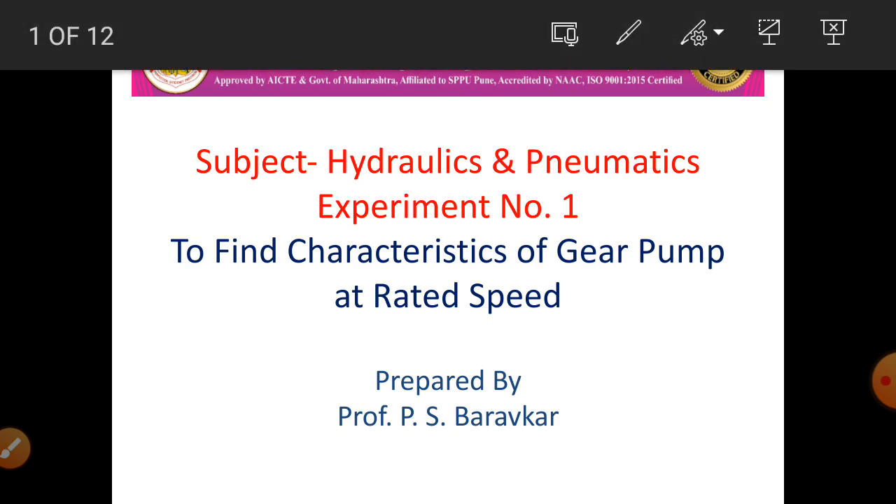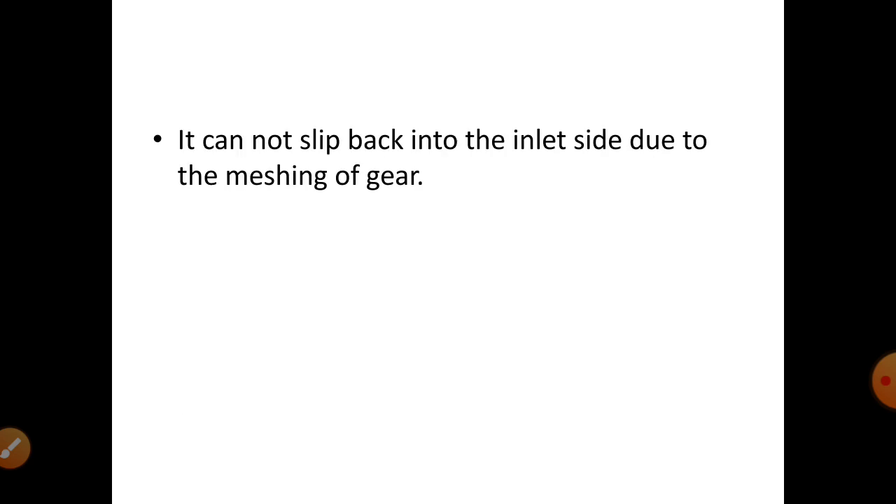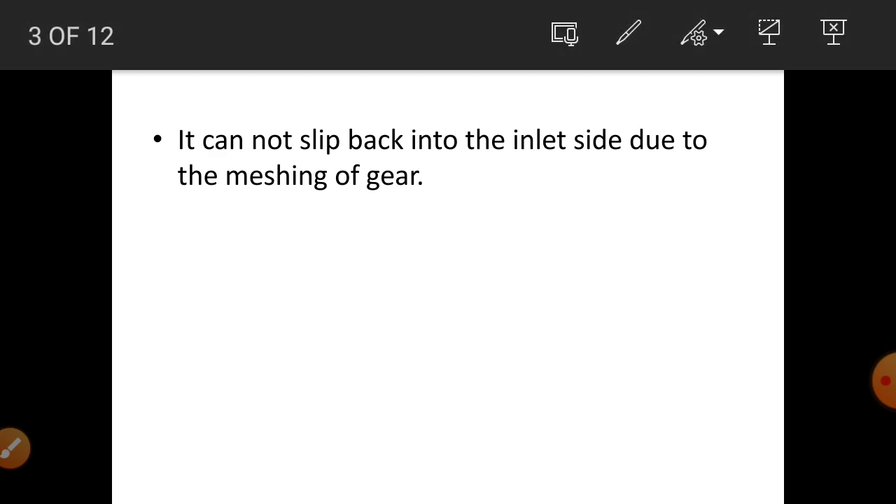The objective of the experiment: a single stage external type gear pump consists of two identical intermeshing spur wheels working with fine clearance inside a suitably shaped casing. One gear is keyed to the driving shaft of a motor and the other is an idler. Oil enters the space between the teeth and the casing, and is carried around between the gears from the suction port to the discharge port. It cannot slip back into the inlet side due to the meshing of the gears.